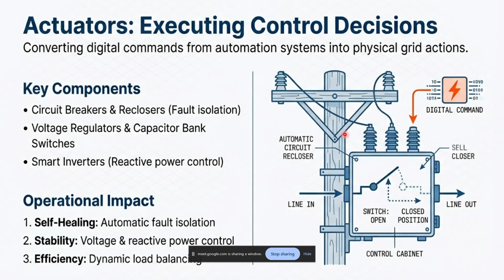So when you have these actuators, what is the operational impact? It helps in self healing, automated fault tolerance, and voltage and reactive power control. When we have self healing and stability, automatically efficiency increases - that is dynamic load balancing. This is a key component in smart grids. If we don't have this kind of decision making - cutting the circuit on or off and increasing load based on demand - we cannot do this. So this is all about physical grid actions.